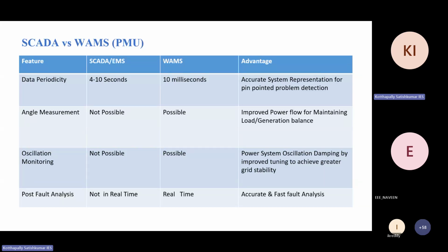And oscillation monitoring, as I told, these oscillations are of low frequency or high frequency. Then to see these oscillations, you need high speed data from the substations to the control center. You need very accurate data, which is not possible in the SCADA system. That's why we are using the PMU system now. So in this PMU system, in this WAMS system, you can see the oscillations. And next, post fault analysis: because you have huge real data, very accurate data with milliseconds and microseconds, you can do post fault analysis from this PMU data.